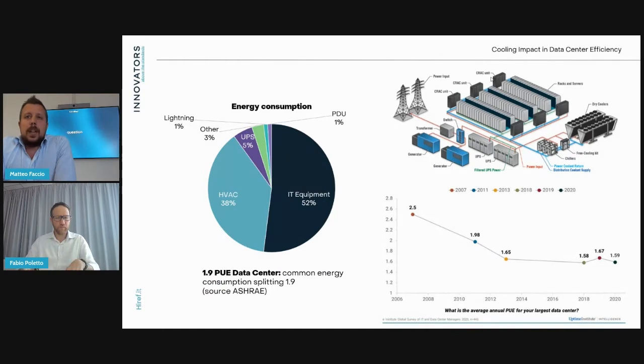At the end of the day, in this graph, we can see what is really used by the end user, by the target. It's only 52% of the total energy consumption. All the rest we can consider waste energy, but it is, of course, mandatory to make the system run properly. Of this rest, almost 40% of the energy is used for cooling. So I think we have a big opportunity to work on this 40% in order to get a major benefit on the PUE.